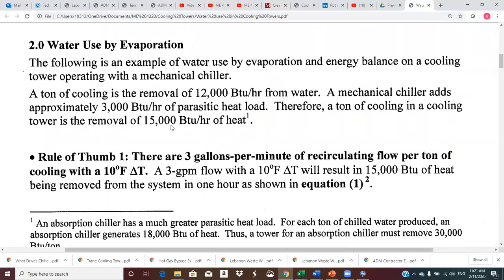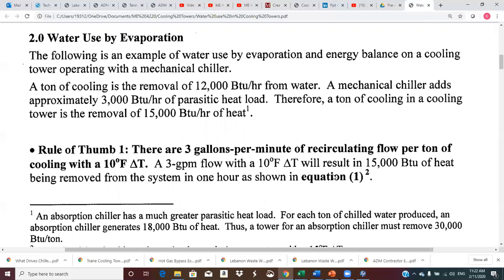Okay, so rule of thumb one, 3 GPM of condenser water per ton of cooling with a 10-degree delta T. So that's our kind of standard number that we've been working with. If you do 500 times GPM times delta T on that, it will come out to 15,000 BTUs of heat removed from the system in 1 hour for each ton, a ton being 15,000 BTUs, or a ton hour being 15,000 BTUs.